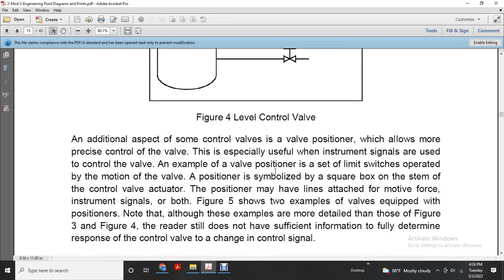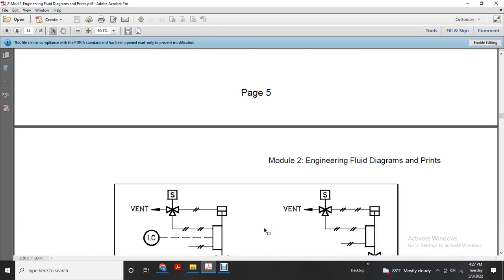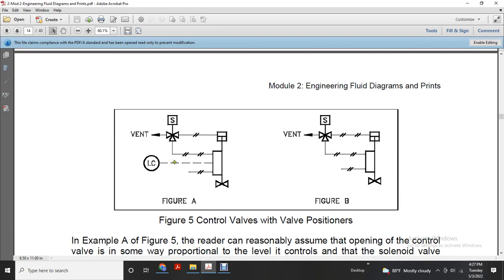Additional aspects: some control valves have a valve positioner, allowing precise control of the valve, especially useful with an instrumentation signal to the control valve. For example, the valve positioner may set limit switches operated by the motion of the valve. The positioner is symbolized with a square box on the stem of the control valve. They may have lines attached for motive force, instrument signal, or both. Figure 5 shows two examples of valves equipped with positioners. Note that although these examples are more detailed than figures 3 and 4, readers still do not have sufficient information to fully determine the response of the control valve to a change in the control signal. Figure 5 shows the control valve with the valve positioner, the solenoid and the starter valve, with the air going to the limit-controlled valve, and then the valve positioners.